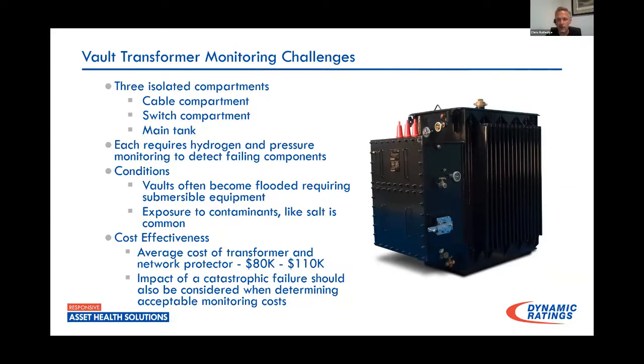So moisture ingress and the integrity of this tank and all the gasketing system is a big factor in ensuring that these transformers stay healthy. A lot of people I'm seeing say, well, we don't worry about pressurizing, or we're not checking pressure. That's a critical point with these transformers, and really with any nitrogen blanketed transformer. I see a lot of concern about moisture monitoring, which I think is vitally important. However, if you have a transformer that is holding nitrogen pressure and you do not have leaks, that really alleviates a lot of the moisture concerns.